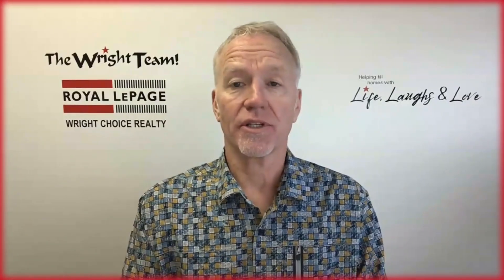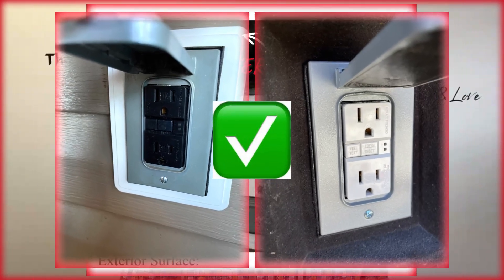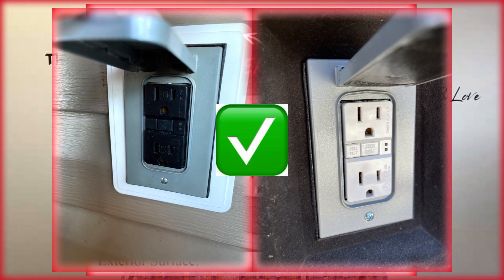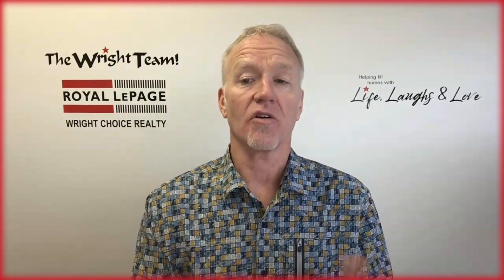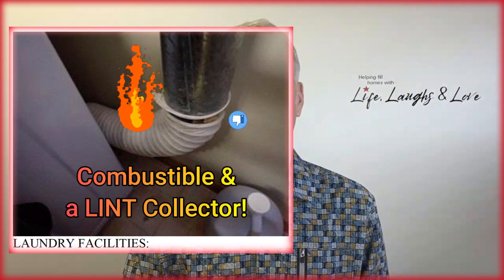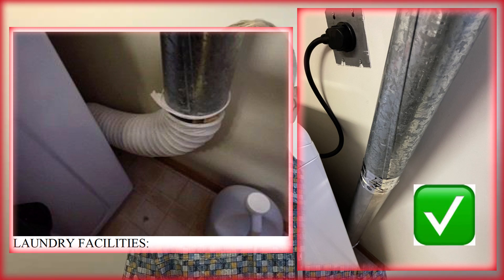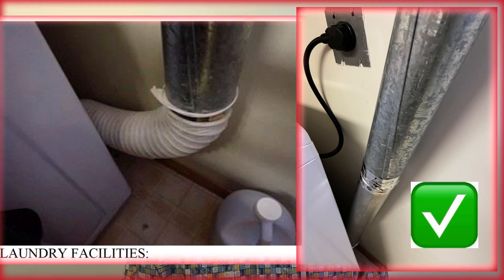For the exterior receptacles, they were not GFCI and they weren't covered, so I've fixed that issue so the next owner won't have to worry about them. In our laundry room, I had the old ribbed venting, which was combustible and a lint collector — basically a fire hazard — so I've changed that over to a hard vent pipe.